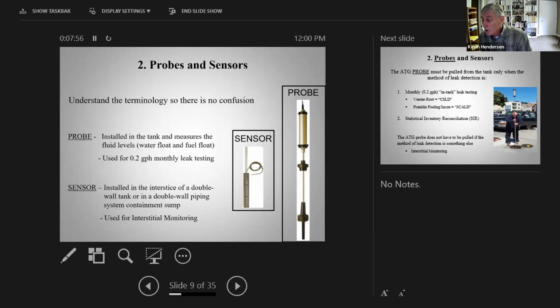When you say something is a probe, what that means is the in-tank probe, the probe that is inside the tank that measures the fuel level and the water level inside the tank. That is a probe. But when you say sensor, that is typically thought of as something that's in the interstice of a double-walled system. It can be an interstitial sensor in a double-walled tank. It can be a simple 208 Veeder-Root sensor that you see the picture of here. That's just their model number, 208. That's what everybody calls them. Very, very common. It's just sitting in a piping containment sump doing interstitial monitoring.